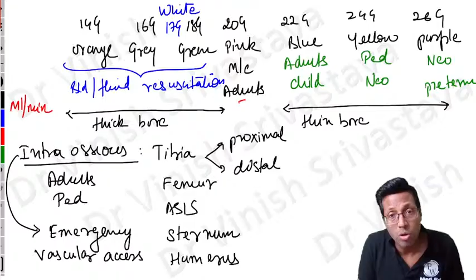If it's going for a child, it's going to be less than that. So around 23 to 25 is for a 24 gauge cannula, almost half of that. In between is 33, so around 33 ml per minute is with the blue gauge cannula. And the smallest one for a neonate or a preterm neonate is around 13 to 15 ml per minute. But when it comes to 18, 16 and 14, they will be much more than 54. So anywhere between 80 to 90, close to 100, is the green one. Anywhere between 170 to 180 is around the gray one. And around 270 to 280 is with the orange one.